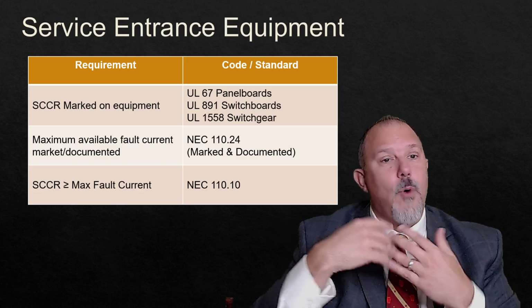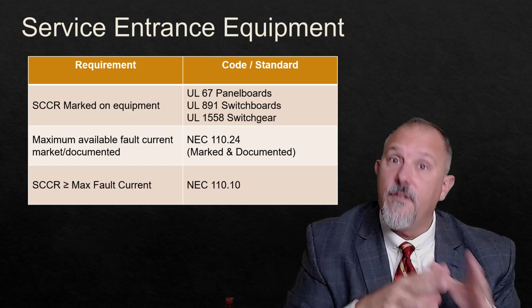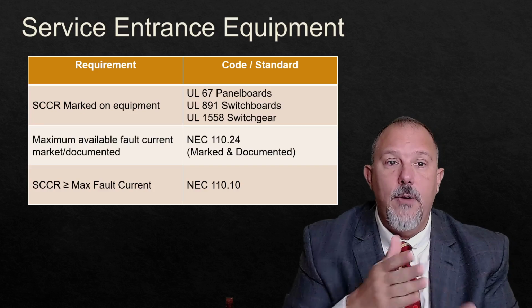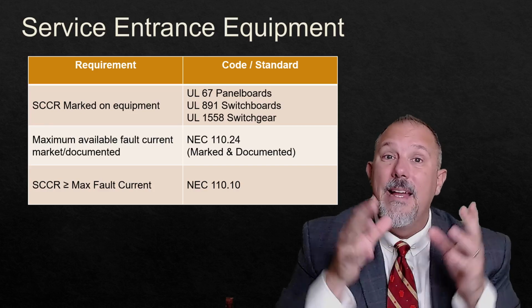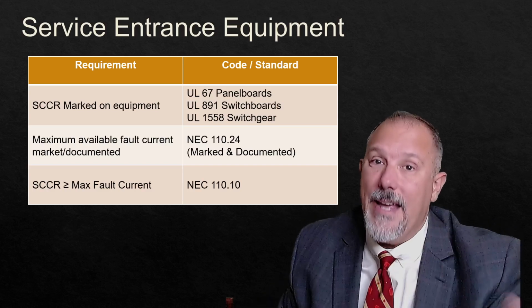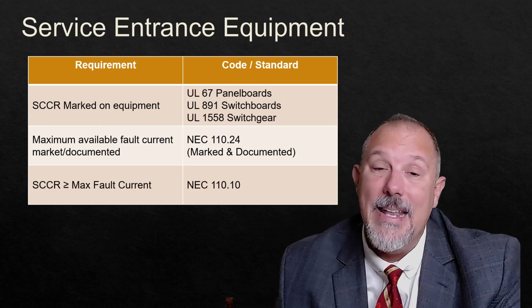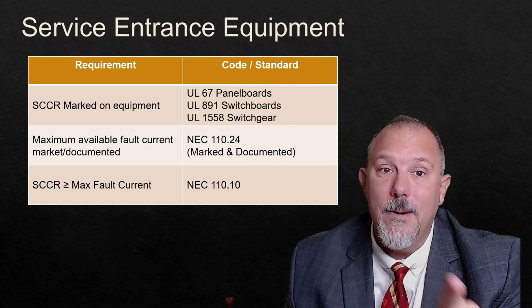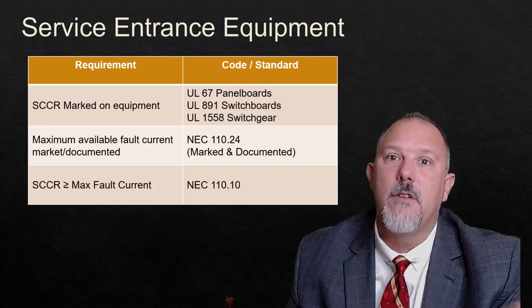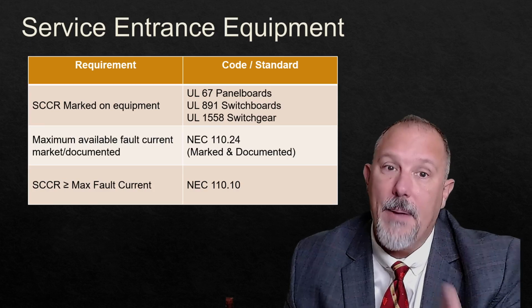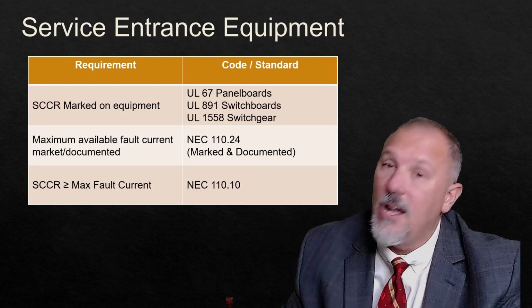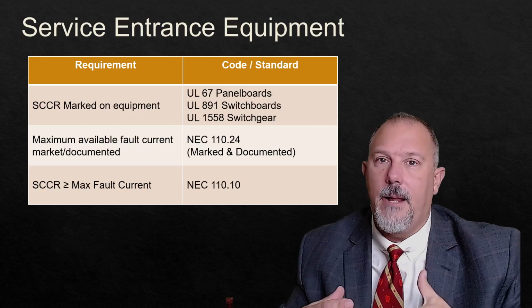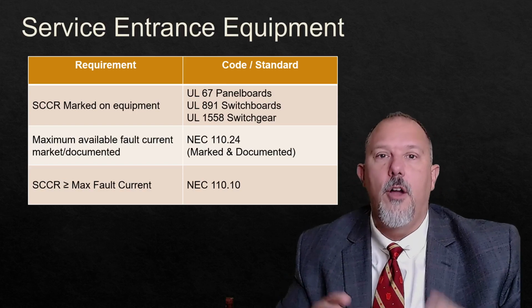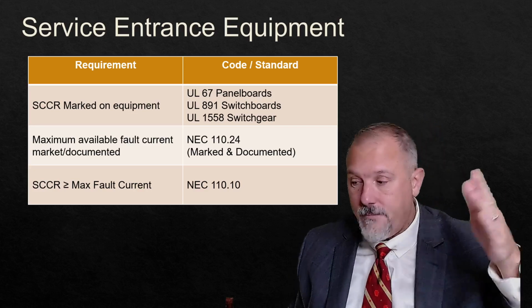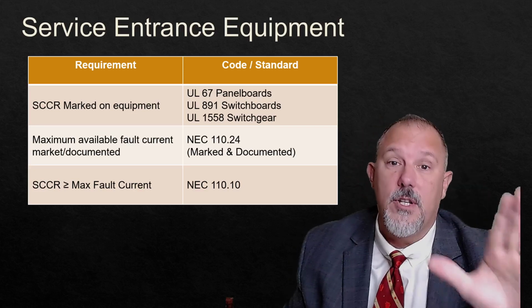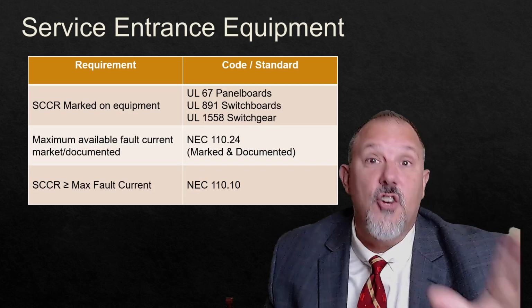Now, here's just a walk through those different areas of the code. Service entrance equipment: you have to have the SCCR rating marked on the equipment. If you purchase and install listed equipment, the UL standards tell you you have to mark those ratings. Now, panel boards, switchboards, and switchgears. Let's talk panel boards real quick because this will give you a little understanding. Panel boards don't mark the short circuit current rating on the equipment. I know. You're probably sitting there going, Tom has gone nuts. He's crazy.